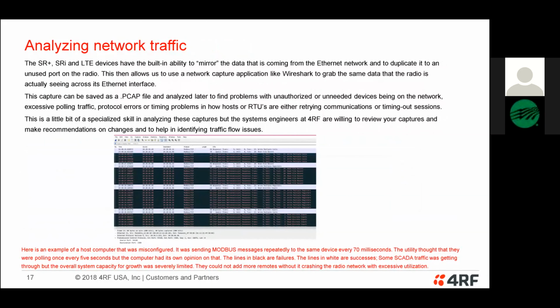I talked a little bit about doing network traffic analysis and capturing the network traffic. And here's an example of another one. This was actually in Charleston, South Carolina. I went out there for this one. The problem was that you see all the black lines on the page, and that's the SCADA host resending requests about every 70 milliseconds. When I talked to their SCADA people, they said, oh yeah, we're only polling once every 5 seconds. We can't understand why the system's not working well. Oh, a 5-second poll shouldn't be a problem.